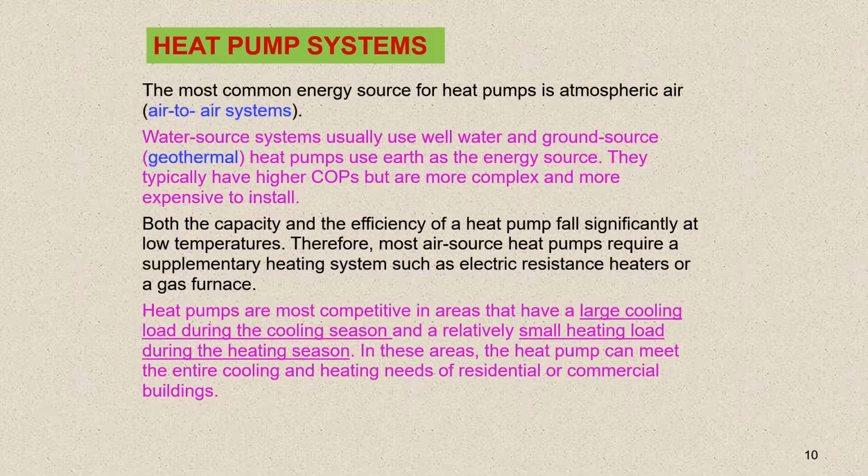The coefficient of performance of heat pumps usually ranges between 1.5 and 4 depending on the particular system used and the temperature of the source. A new class of recently developed heat pumps that use variable speed electric motor drives are at least twice as energy efficient as their predecessors.